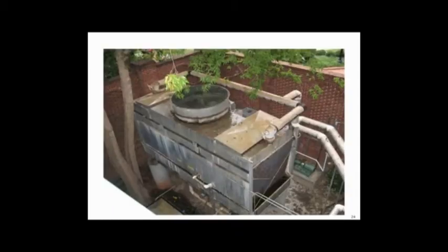Here's another one for you. I like towers. I think they're pretty. For some reason, some people do not think they're pretty. They want to put walls around them. You put walls around them, you have the same issue again. You're not going to get rated capacity. In this case, at least the bricks had a few holes in them. You're going to design something like this, go to your vendor, find out what the requirements are, find your tonnage, and they can help you figure these walls out if you want to do it.